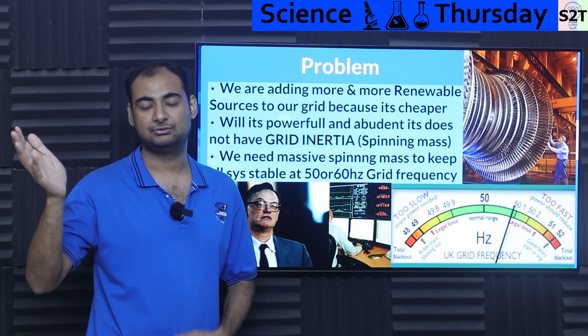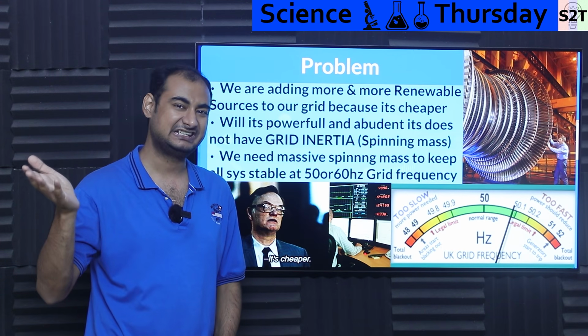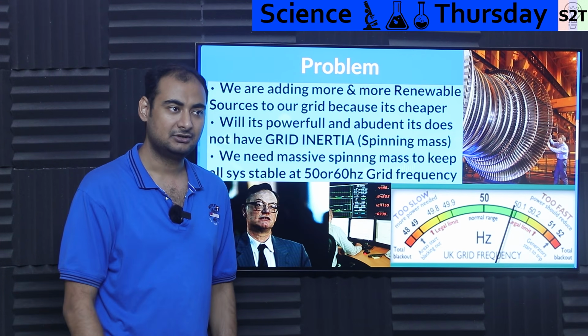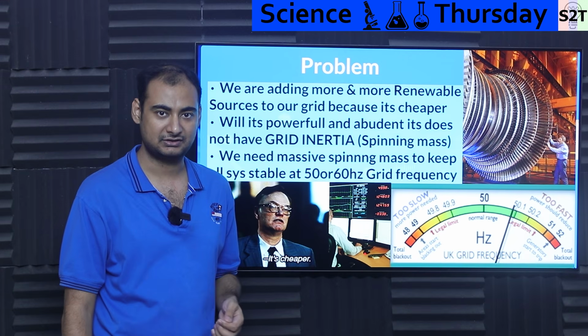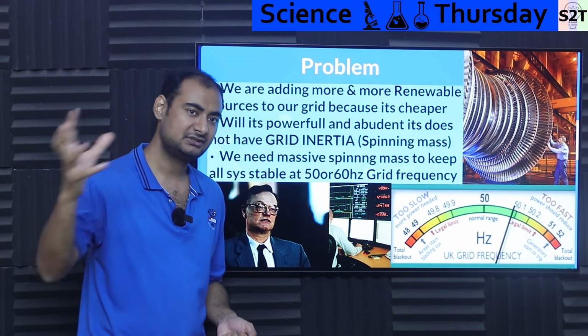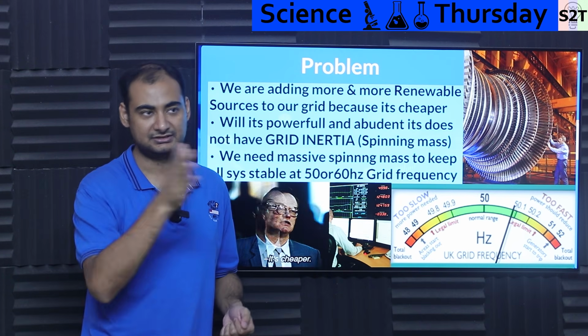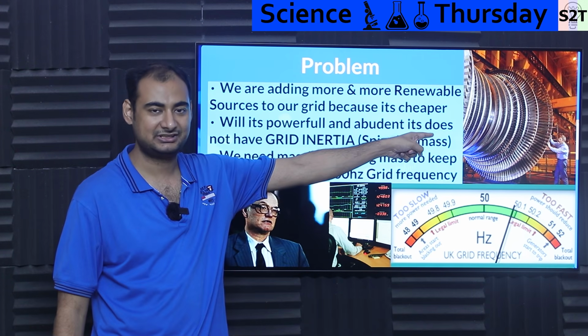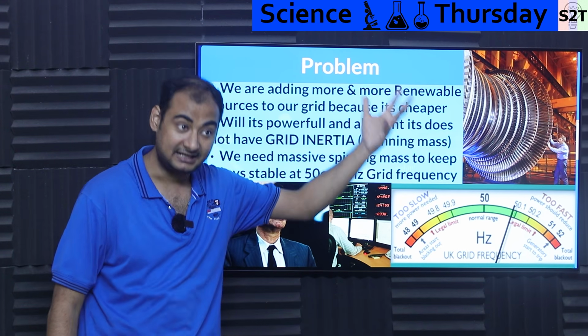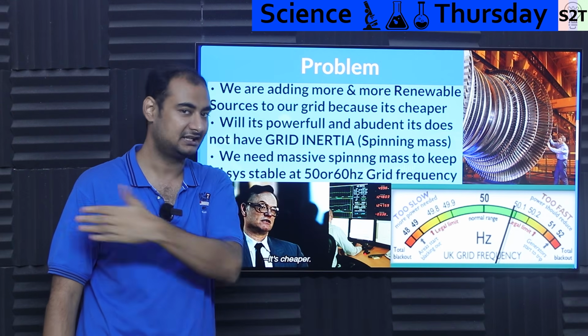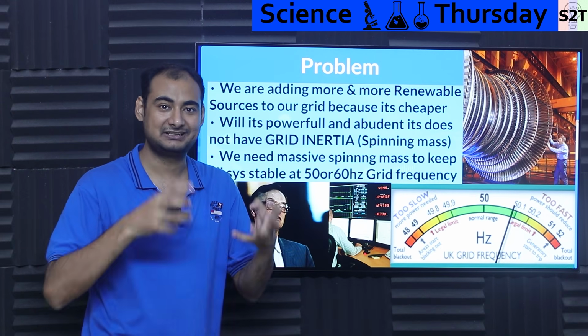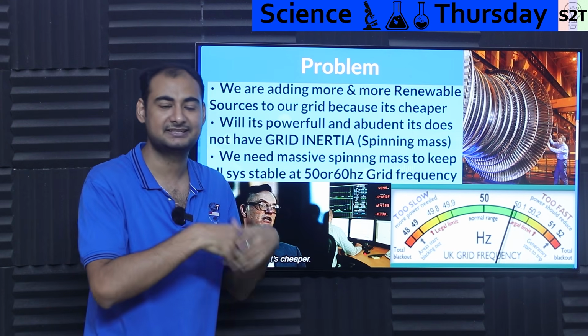Let's say you had that same steel furnace working, and then you turn it off. Why wouldn't you get ludicrously high voltage running into your system? It won't, simply because now you've stopped leaching the energy. But you still have higher steam pressure, spinning at the expected load, except that load has been removed. What happens? The rotor is now free, it doesn't have the magnetic resistance it was designed for.